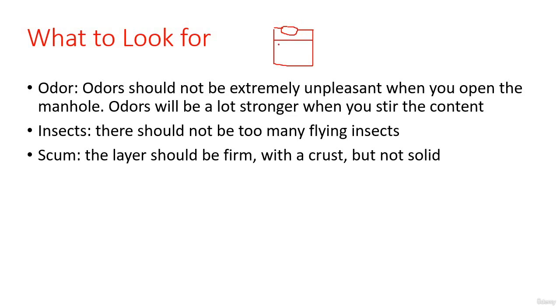When we open this manhole, we have to look for, first of all, the odour. Odours should not be extremely unpleasant. Of course we have odours, but they must not be extremely unpleasant. If you disturb the contents, the odour will be a lot stronger. The odour must not be extremely unpleasant because there is the formation of a crust made by oil and scum that provides some sealing to the system. Also, you must pay attention not to have insects — there should not be too many flying insects. These parameters are signs of a good working septic tank.